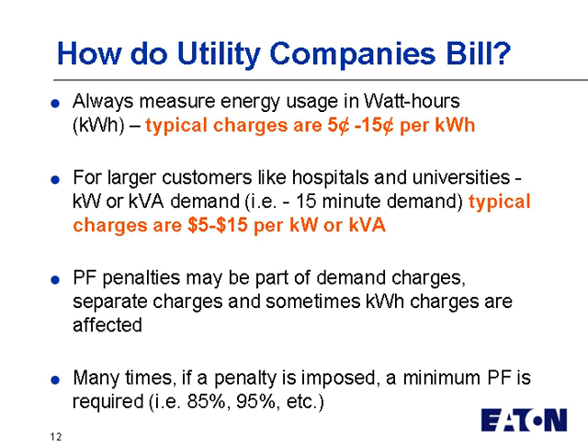Now again, part of the reason you don't necessarily look at the bill is because different parts of the company or the facility pay the bill versus actually would be the person to analyze the bill. And we want to talk about how utility companies bill so that we can understand what's important on that bill. They always measure usage in kilowatt hours, for example, and that's what we're used to in our residence. We typically have charges that are something like 5 to 15 cents per kilowatt hour. For larger customers, like most of you, they charge a kilowatt or kVA demand, and that's typically a 15-minute average number. So, for example, if you're using 1,000 kilowatts for the past 15 minutes, that might be the most you used over the past month. They're going to charge you a 1,000 kilowatt demand charge as well.